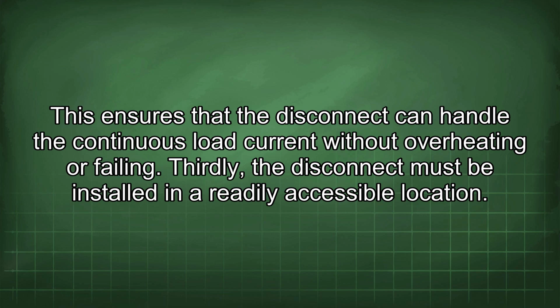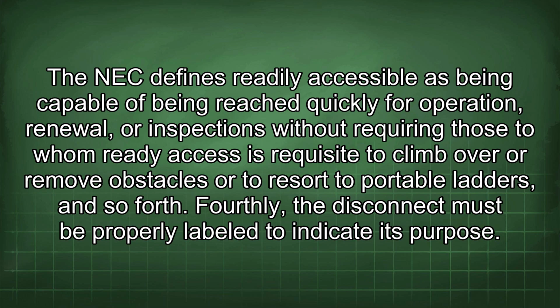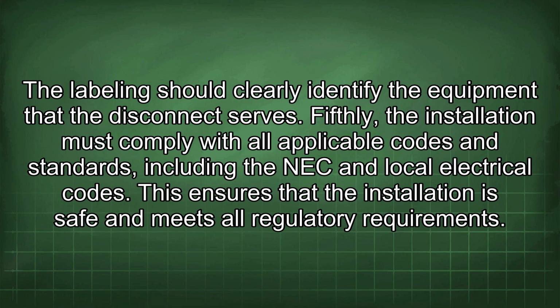Thirdly, the disconnect must be installed in a readily accessible location. The NEC defines readily accessible as being capable of being reached quickly for operation, renewal, or inspections without requiring those to whom ready access is requisite to climb over or remove obstacles or to resort to portable ladders, and so forth. Fourthly, the disconnect must be properly labeled to indicate its purpose. The labeling should clearly identify the equipment that the disconnect serves. Fifthly, the installation must comply with all applicable codes and standards, including the NEC and local electrical codes. This ensures that the installation is safe and meets all regulatory requirements.